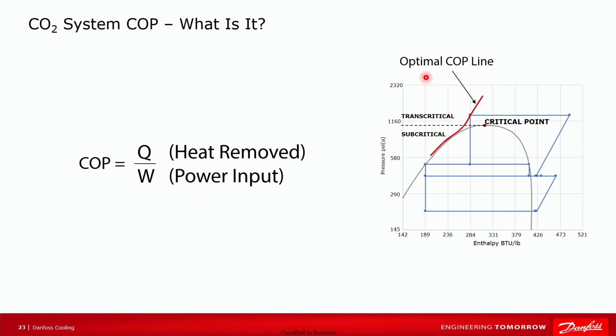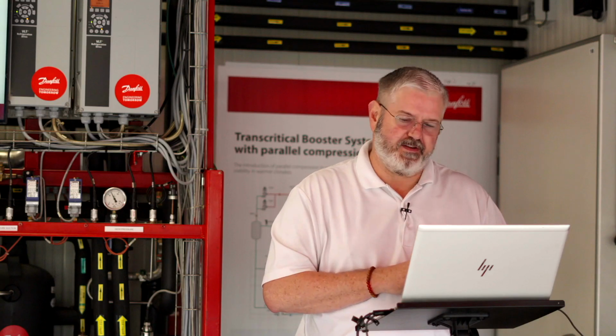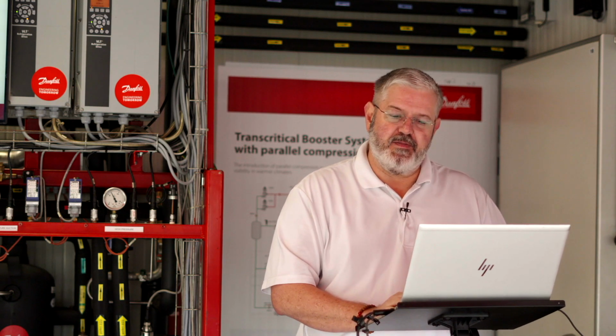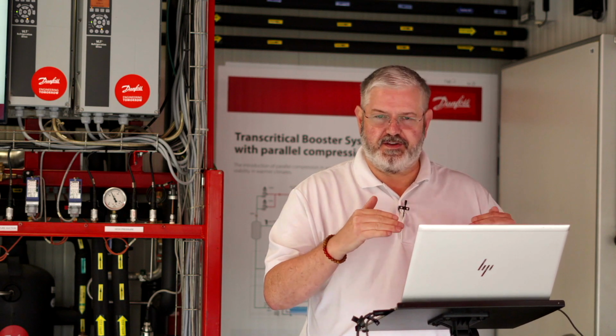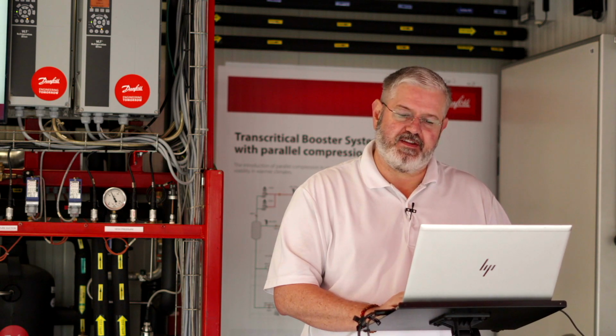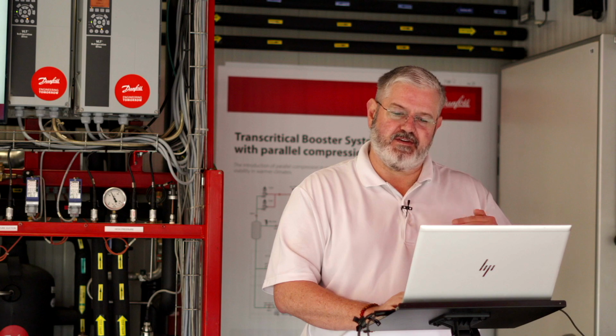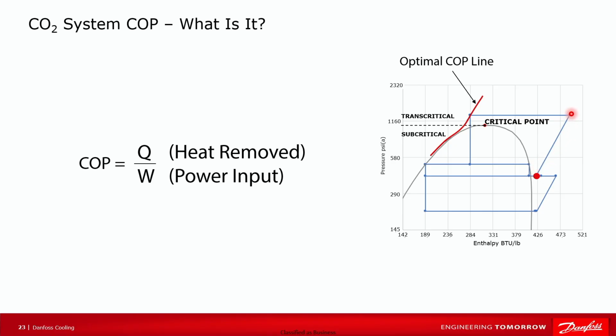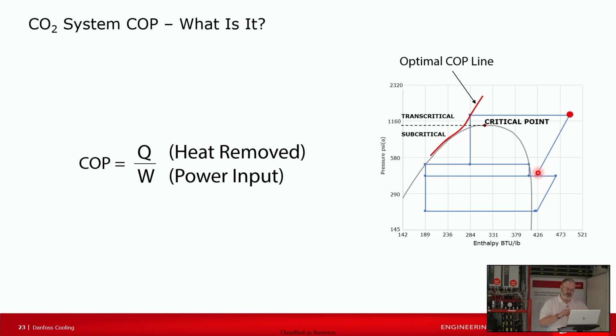So I mentioned earlier the optimal COP line. I did an exercise several months ago. There's a formula about a mile long that would take you all week to do if you're a newbie to it like myself. It tells you, for given conditions and a given displacement of a compressor, how much energy it takes to compress the low temp suction gas and raise it up to gas cooler pressure. The pack controller is performing that calculation on an ongoing basis. It knows the displacement of all the compressors, how many compressors are active, the ambient temperature, and the pressure leaving the gas cooler.